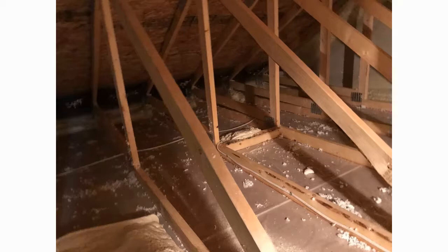Because a lot of builders just throw the screen on, right? Mm-hmm. And so they have no backflow on the roof end, and then backflow on the fans. The cheaper ones are really poor. So you're getting a lot of air leakage both ways, cold coming in, more moist air going up. Yeah, all the time. I think that's maybe part of the problem, but that's a pretty small part of the problem.